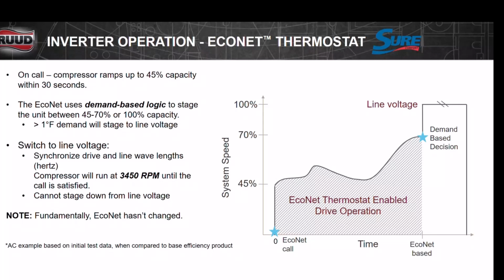We're maintaining temperature. If it gets outside the parameters, then we turn it on high to get it back down. It's going to run at high speed until the end of the cycle, and it's going to start off again, running like this. 45%, and make its way up to 70, and then bam, line voltage comes in, it goes up. 45%, it can run up to 70% here. It's just depending on the time it's running. Okay. As it runs longer, the faster the speed it's going to go, because it can see the load. But once it gets to that 70% is whenever it swaps over to the contactor and it picks up the high speed.